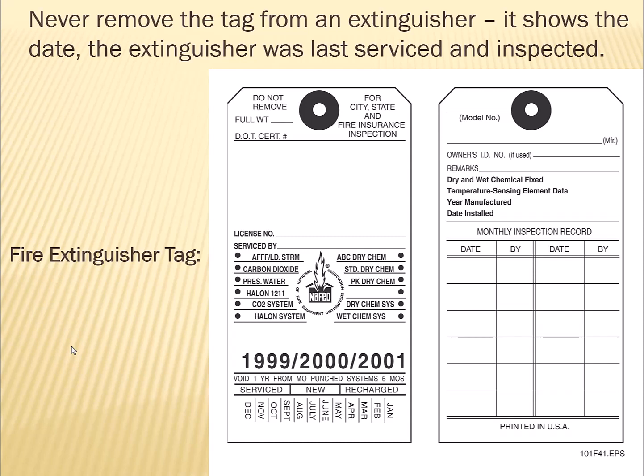But anyways, I digress. So that's the thing to remember, so you don't get laughed at or made into a fool at some point. When you check the tag to see what the date is, the date isn't the date that it expires. It's the date that it was serviced. And when that date is more than 1 year from the current date, then you know it's expired.